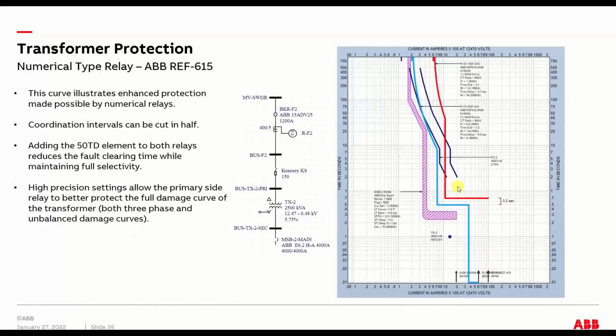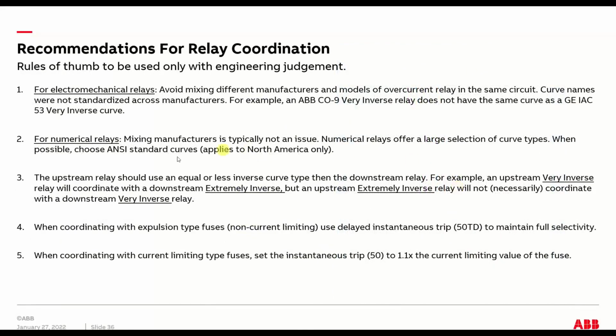Since we're running out of time, I'm going to speed through some of that stuff and just get down to some basic recommendations for electromechanical relays. I think I've been through this. The various manufacturers all had different curves with the same name. So there may have been like a CO9 very inverse from ABB, wasn't the same curve as what GE called a very inverse, which would have been an IAC 53.